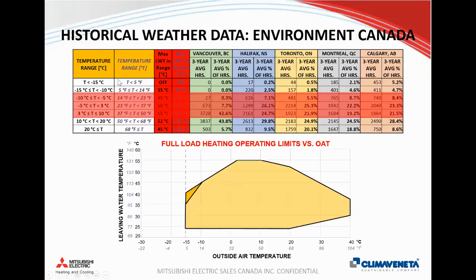So the reason why in the last slides I was showing some different temperatures, showing where the temperature range is below -15, between -15 and -10, -10 to -5, -5 to +3, +3 to +10, +10 to +20, and above 20, is really to demonstrate what's referred to as the operating envelope for air-to-water heat pump technologies. So the heat pumps available from Mitsubishi can operate continuously down to -15 degrees Celsius.